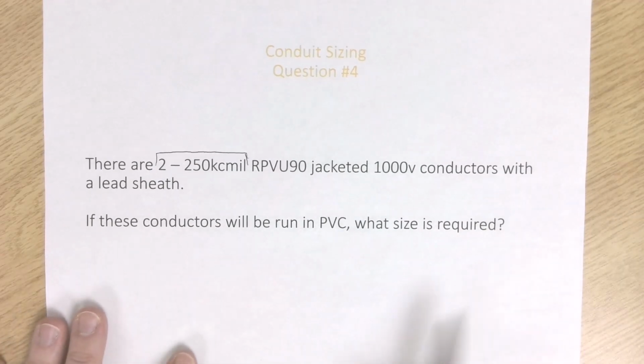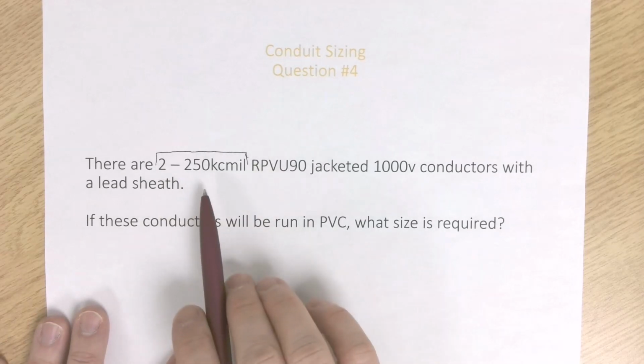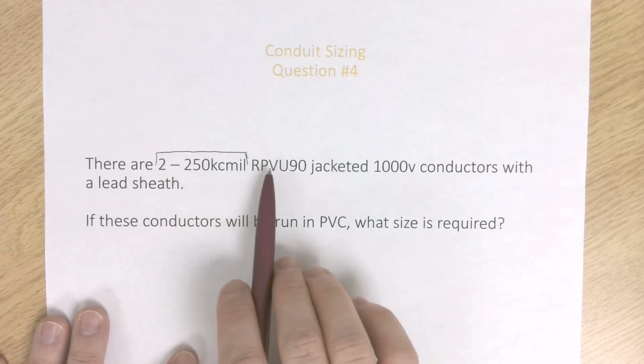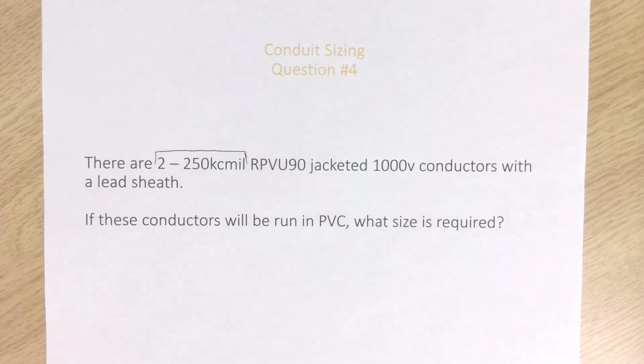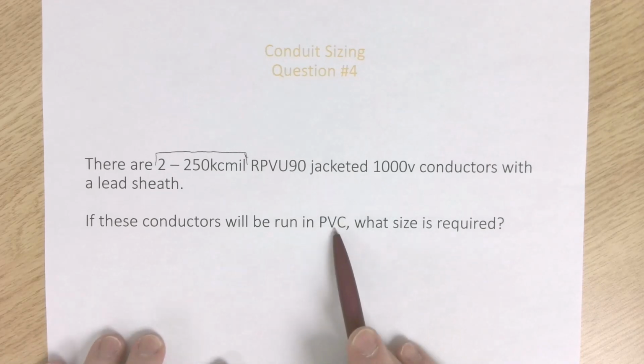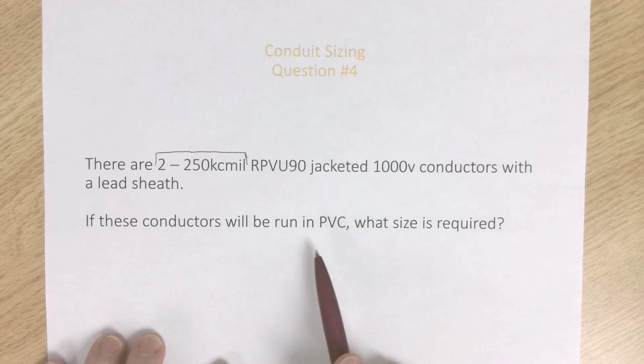So you might think, okay, I'll go to whatever table has these wires. But we need to stop for a second and think about Section 10. We must always keep Section 10 happy. What is my bonding means here? Because it doesn't actually have something that would satisfy my bonding means. Because it's PVC, that's plastic. So that's not my bonding means.